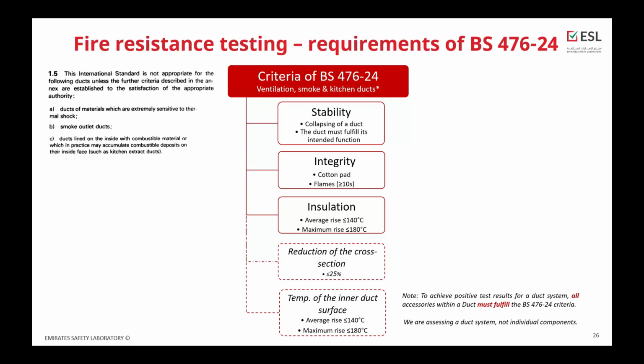Why are the next two criteria, reduction of the cross section and the temperature of the inner duct surface, presented in a different way? This is because the standard, in clause 1.5 in the scope, is telling us that the international standard is not appropriate for the following ducts unless the further criteria described in the annex are established to satisfy the appropriate authority. So if the authority will accept this, you can use this annex to establish the criteria.